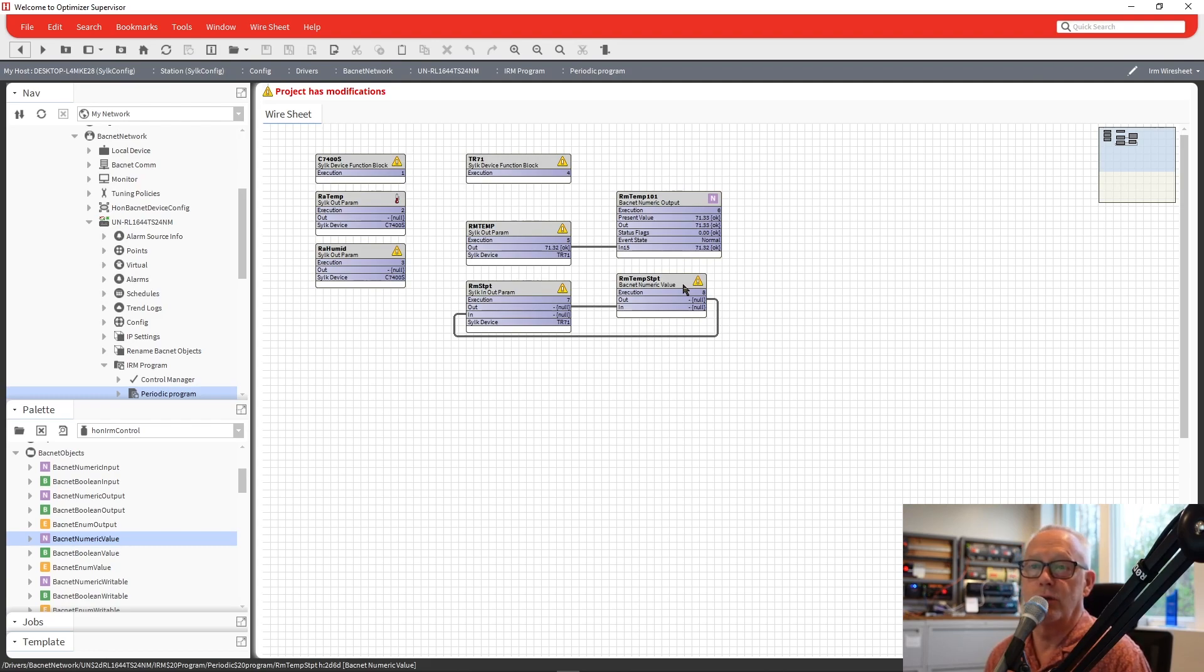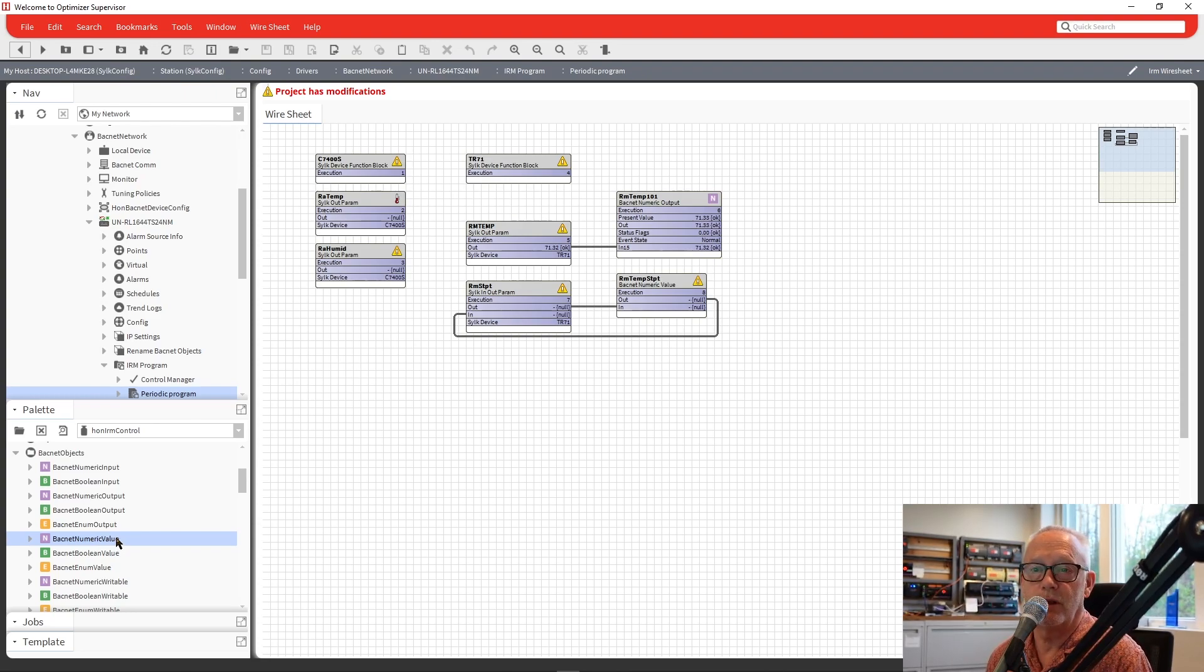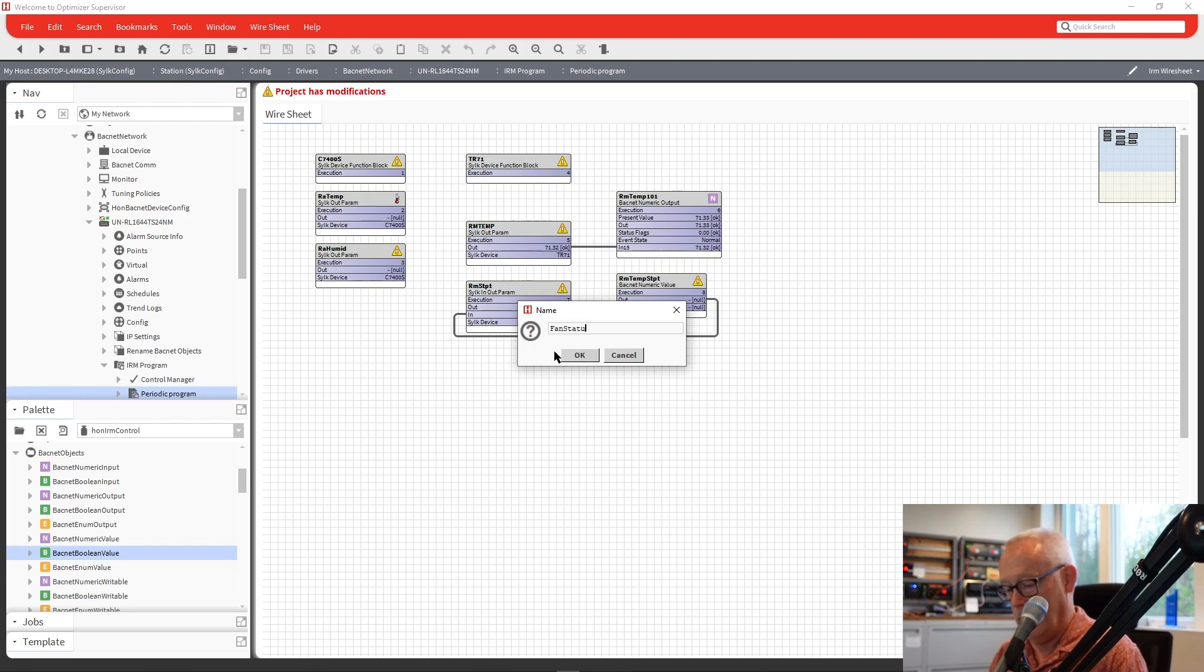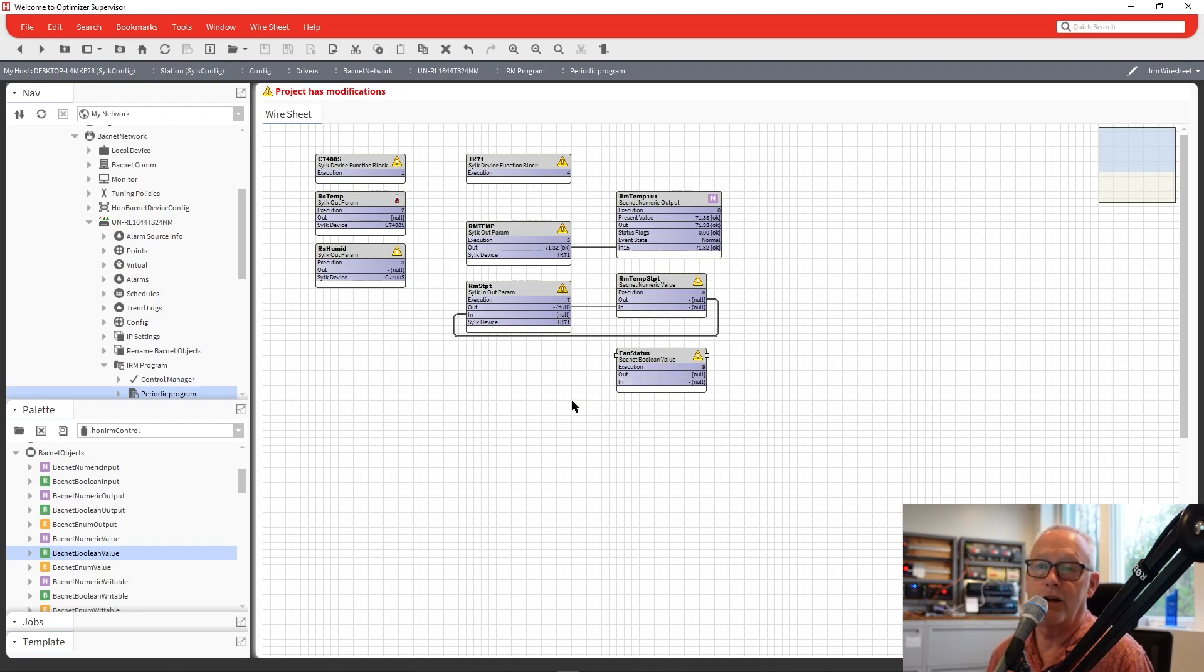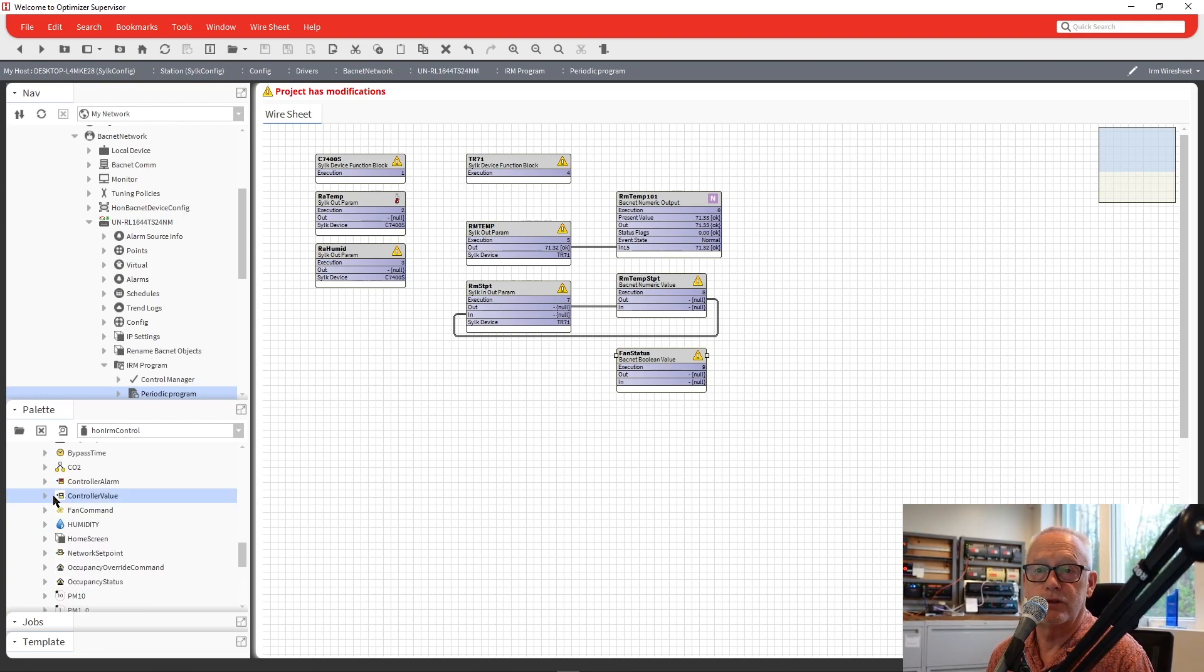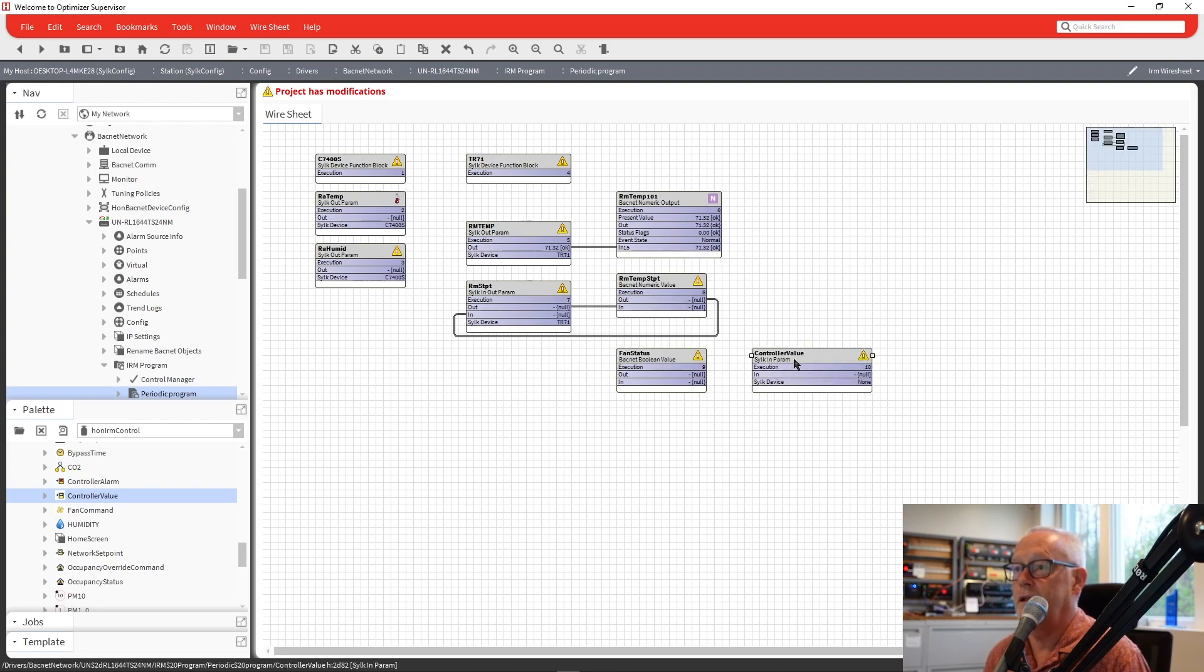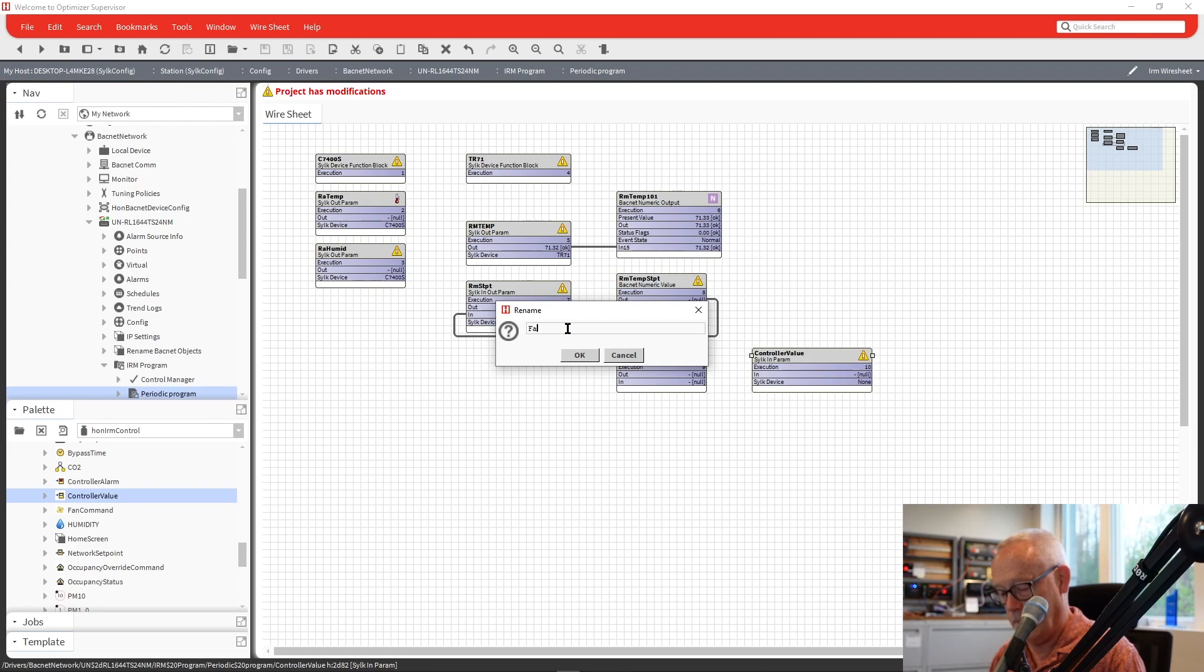We could also then add other points. So you have a, I don't know, we have a fan status or something like that. We could come in here and grab another point and I'm just going to call it fan status. And if we want that to be brought into the Sylk device, we have to add another Sylk parameter. So if we go back to our parameter list and we look for a controller value and you'll see here, it's narrow pointing into the Xeo. So I'll drag that on here. We can actually bring it over here, drop that in and we'll call it fan status.